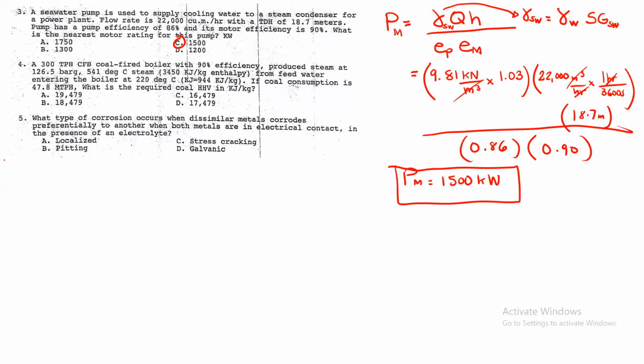So, number 4. At 300 TPH, a CFB coal-fired boiler with 90% efficiency produced steam at 126.5 barg, 541 degrees Celsius, with 3450 kilojoules per kilogram enthalpy, from feed water entering the boiler at 220 degrees Celsius, where it is equal to 944 kilojoules per kilogram. If coal consumption is 47.8 metric tons per hour, what's the required coal higher heating value in kilojoules per kilogram? So we are looking for the HHV, or higher heating value.